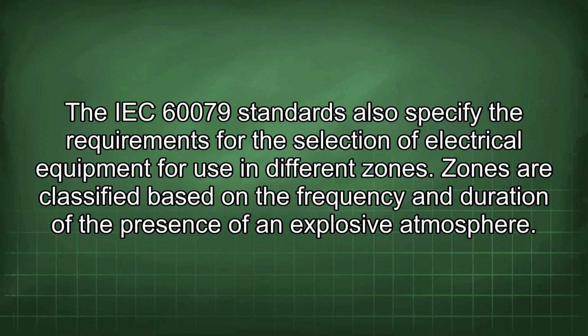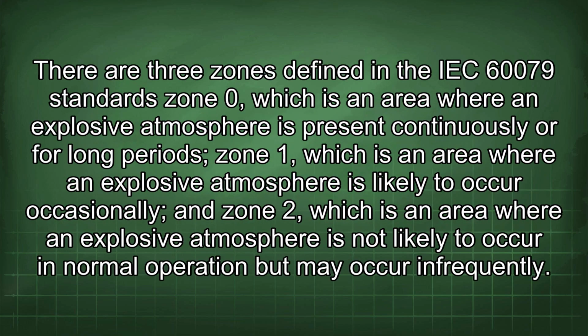The IEC 60079 standards also specify the requirements for the selection of electrical equipment for use in different zones. Zones are classified based on the frequency and duration of the presence of an explosive atmosphere. There are 3 zones defined in the IEC 60079 standard. Zone 0, which is an area where an explosive atmosphere is present continuously or for long periods. Zone 1, which is an area where an explosive atmosphere is likely to occur occasionally.